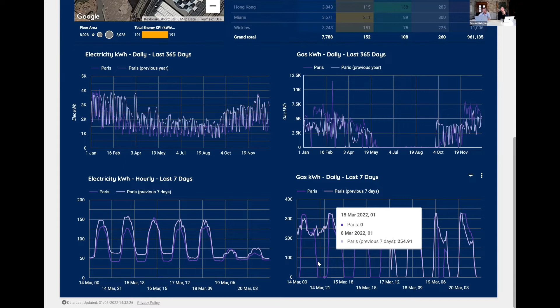On the gas side, you can see similar trends here, where again, the dark purple trend here is this week. In this instance, we're now shutting the boilers off at 7 o'clock in the evening. They're at zero until maybe 7 or 6, maybe even the following morning, whereas the week previous, they weren't being shut off at all, so you had gas consumption right through the night.